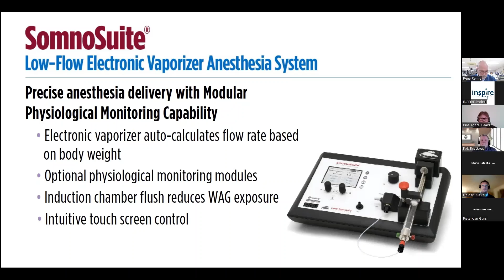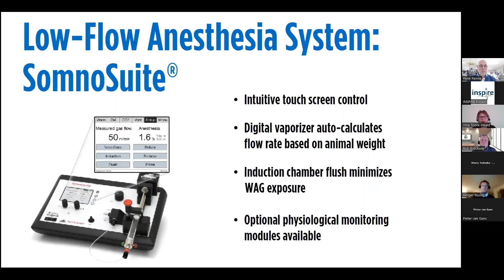Here's how to use it. You take the syringe, fill it with isoflurane, place it on a syringe block, and then, as you can see, the black block in the middle of the unit is your vaporizer block. In comparison to the traditional vaporizer block, it's a lot smaller, and again, it's electronic, so it does not require annual calibration.